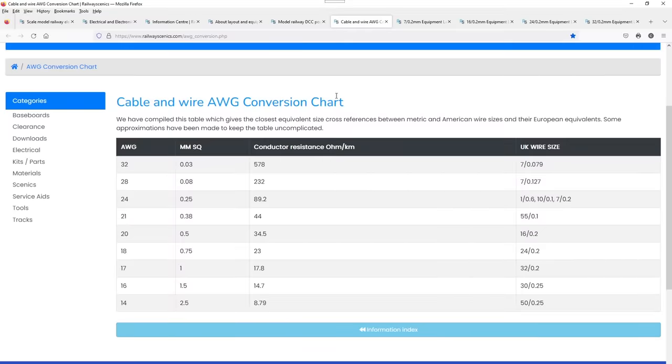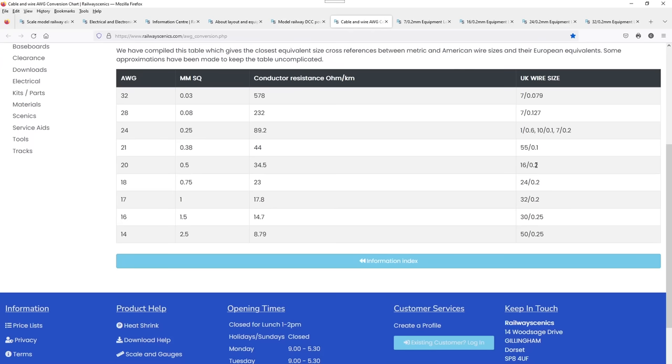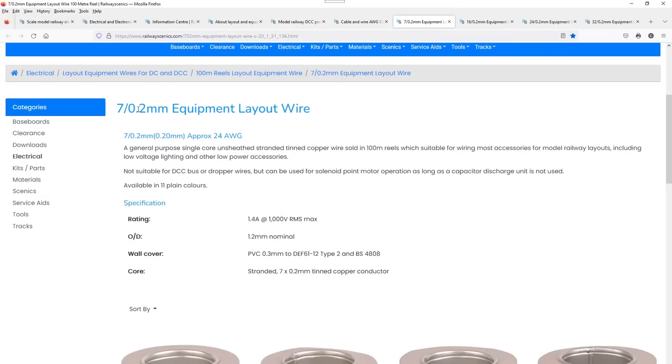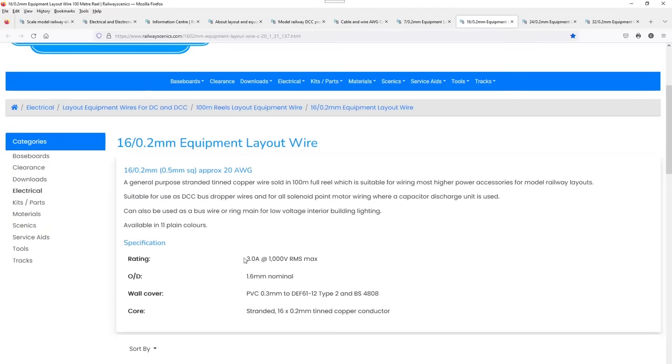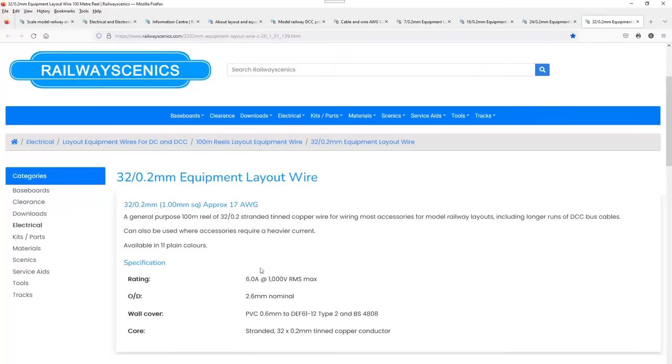I mentioned earlier the differences in cable size. The American Wire Gauge, millimetre cross-section, and the UK wire size. For example, 16/02 is also known as 20 AWG and it's half a millimetre cross-sectional area. Wire sizes we use: 7/02 means seven strands of 0.2mm wire, rated at 1.4 amps. 16/02 is rated at 3 amps, 24/02 is 4.5 amps, and 32/02 is 6 amps.